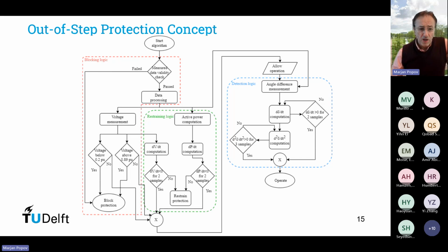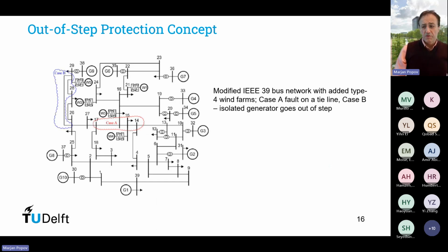This is a flowchart of the algorithm, which, as can be seen, consists of 3 major parts. The first is the blocking. The second is the restraining criteria, and the third is detecting logic and operation, which means that normally we have to pass through all these three in order to operate. And we have tested this algorithm on many different cases that I'm going to explain now here, before we were sure that this algorithm really is reliable.